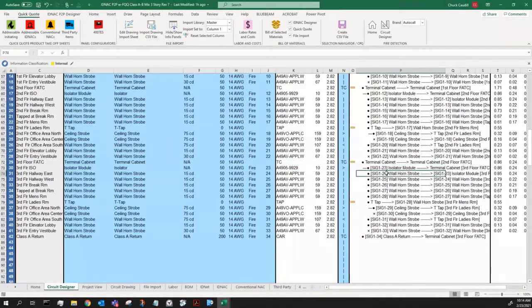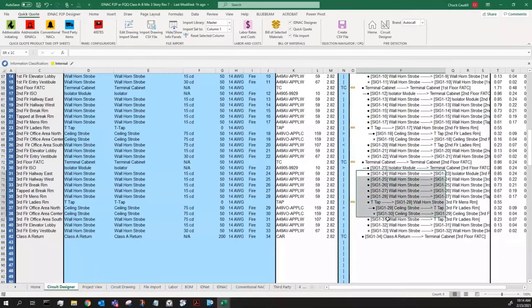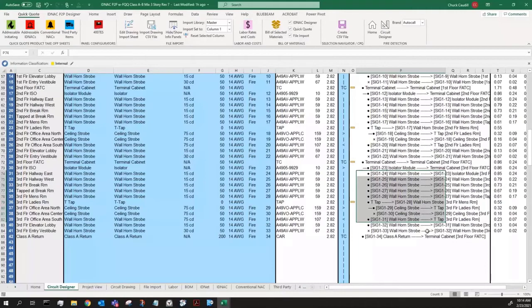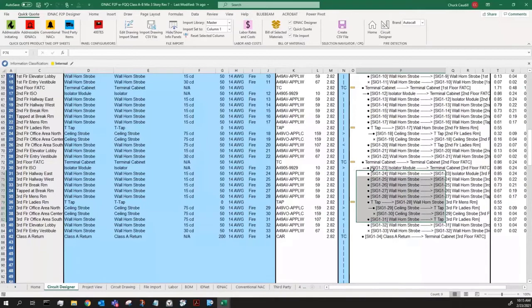Then all the devices below there are either straight line to it or even through a tap in the middle to show that now I'm out in the Class B section. I can tap as many times as I want in that Class B. A short circuit anywhere on this and these devices will get stopped at this isolator module and it won't affect the rest of the building.